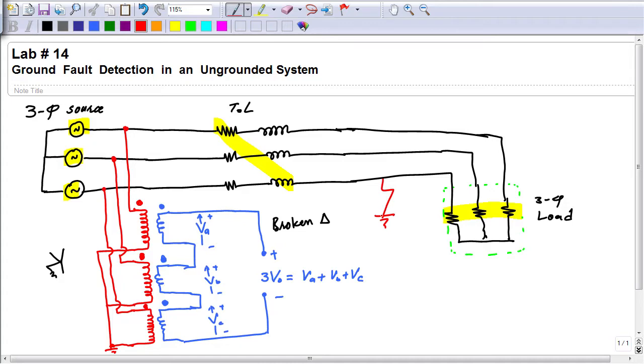Look here, due to this grounding path, the voltage across the third phase, which is connected to this VT, will collapse to a low value, less than the normal value. If this is the loading condition, the voltage across this voltage transformer will be the voltage across this transmission line, between this terminal and ground. Across the primary of the remaining two phases, A and B, we have full system voltage, and across the third we just have the voltage across the transmission line.